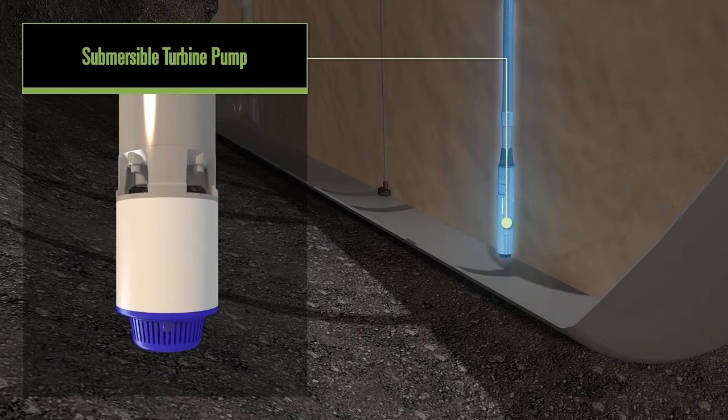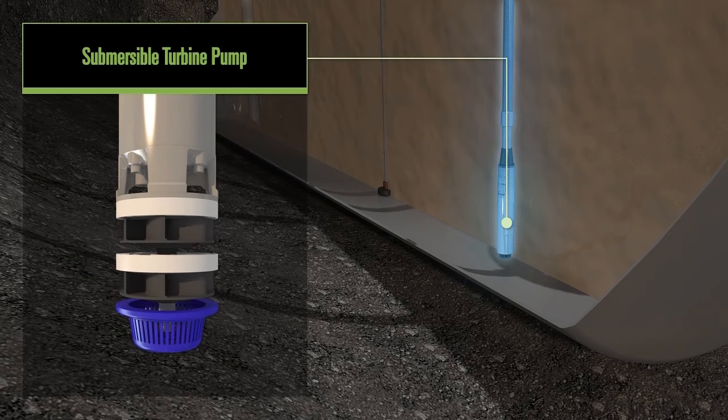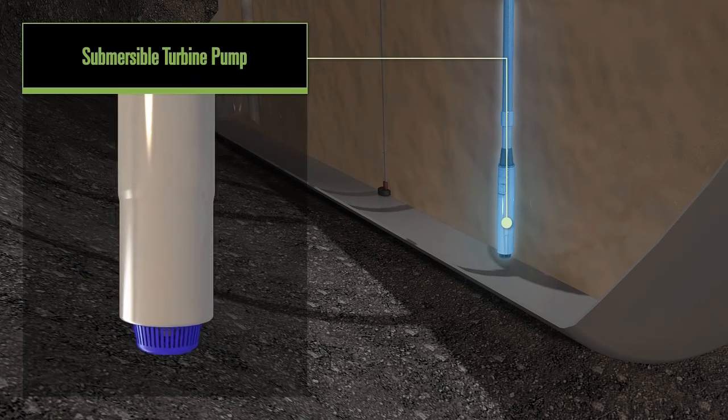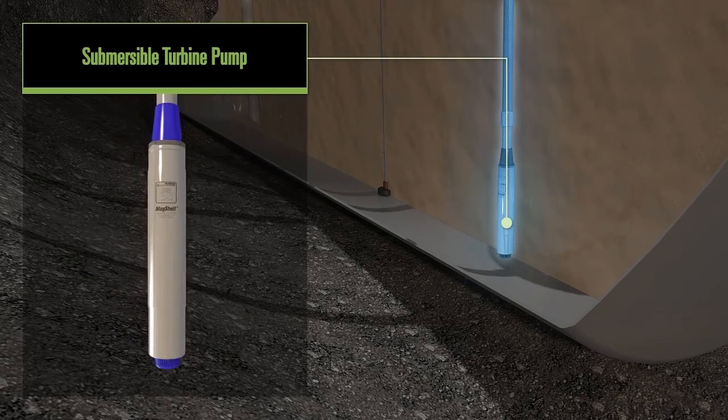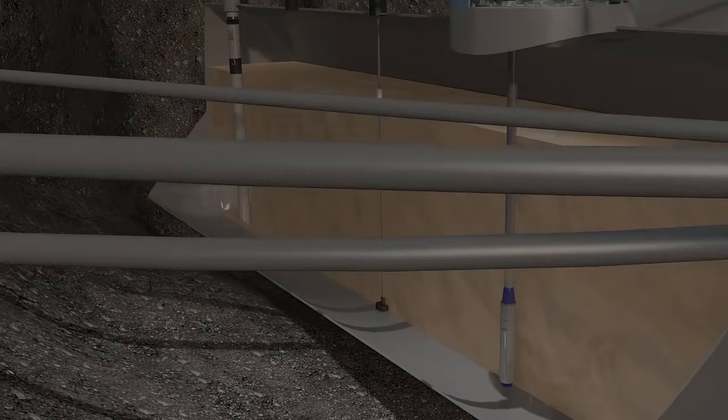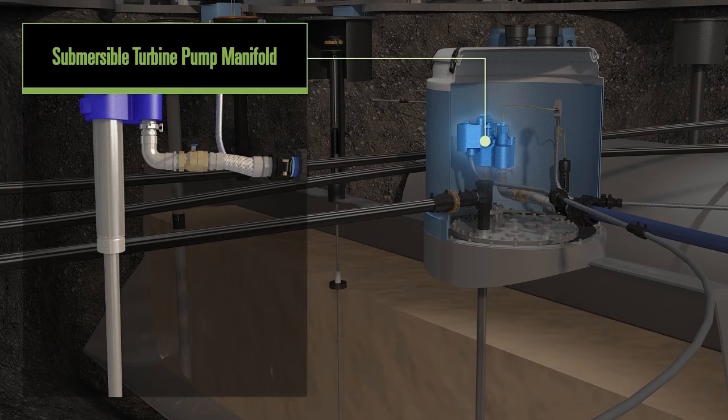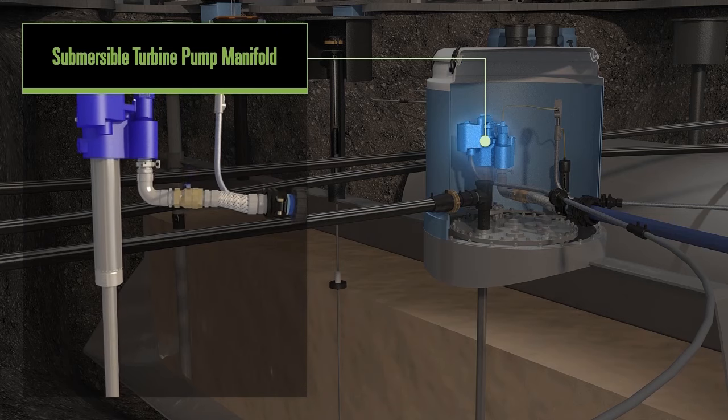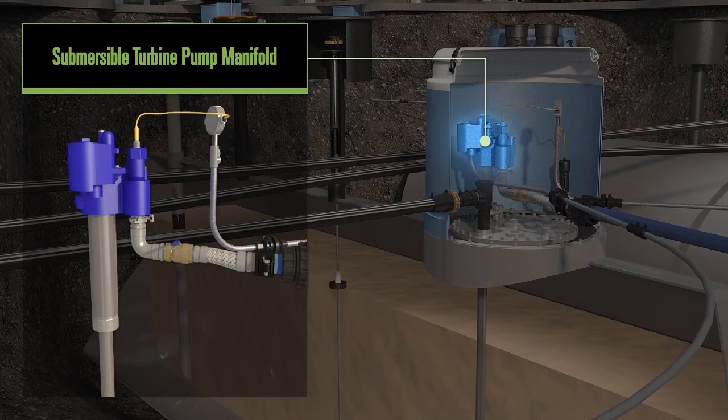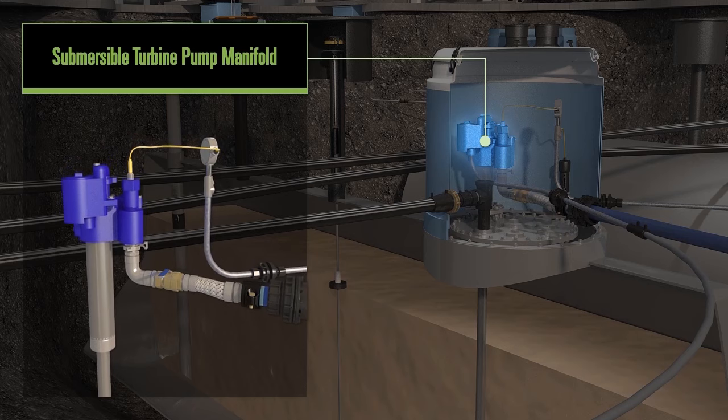Our submersible turbine pump is a centrifugal design, which means that fuel is forced up through the pump by spinning impellers to create pressure and flow out the top of the submersible pump, known as the manifold. The manifold houses the electrical supply to the motor and also the pathway for the fuel to get to the pipe.